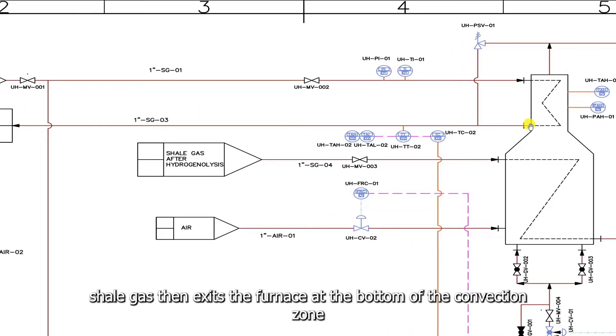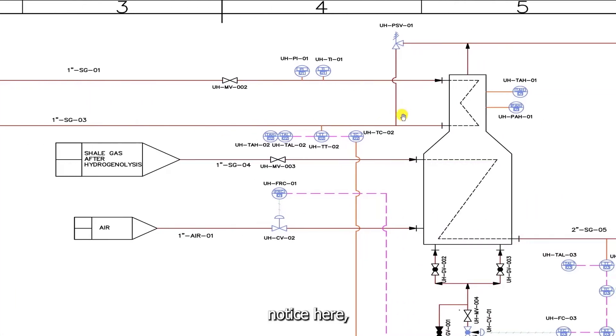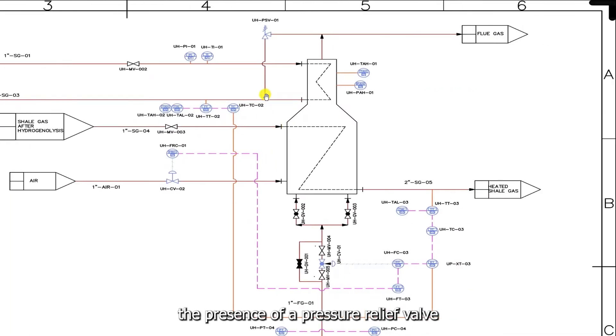The heated shale gas then exits the furnace at the bottom of the convection zone and flows through a one-inch pipe to feed the hydrogenolysis. Notice here the presence of a pressure relief valve. This is a safety device which in case of overpressure will pop fully open to relieve excess gas to the flue gas piping network.